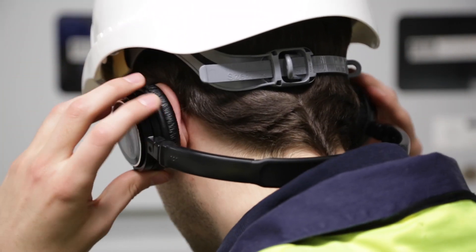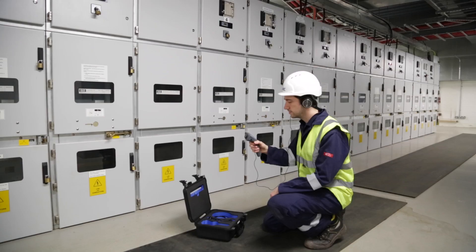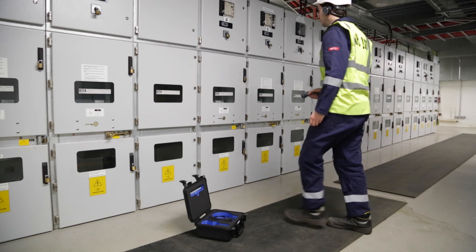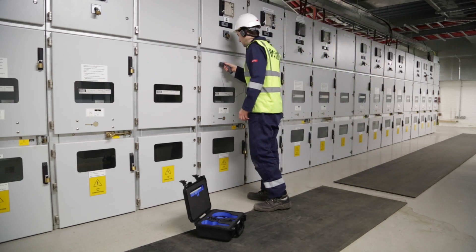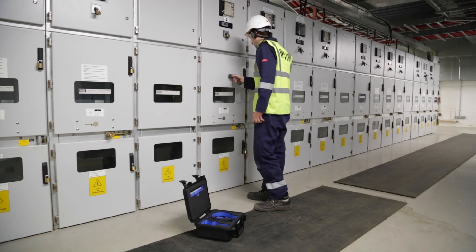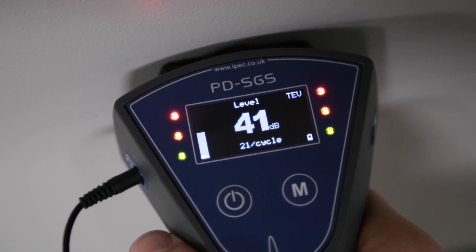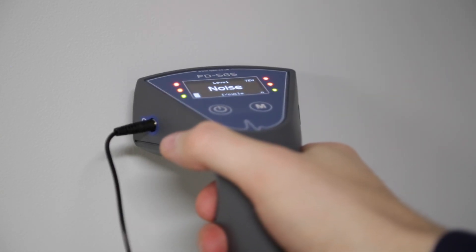In noisy environments, the headphones can be worn to ensure maximum performance. Sometimes electrical equipment or heavy plant can generate high levels of electrical noise that are similar to partial discharge. The PD-SGS software can recognise typical characteristics of electrical noise and warn the user that the levels recorded could be caused by a non-PD source.